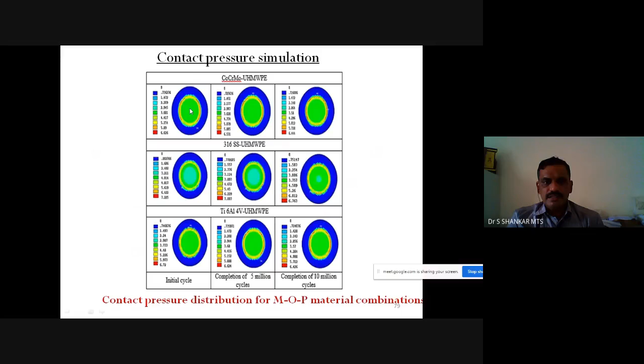You can see this for different combinations, metal on plastic or metal on metal. We can find the linear wear for cobalt chromium on UHMWPE, 316 stainless steel on UHMWPE. This is the use of the software. If a surgeon is using only UHMWPE, at the end of 10 million cycles, approximately equal to 5 to 6 years, sometimes up to 10 years, this may be the wear. If you validate with experimental results, then by changing the material property we can predict wear and say that approximately this is the wear. If you go with CoCr on UHMWPE, your material removal will be 0.4 to 0.5.